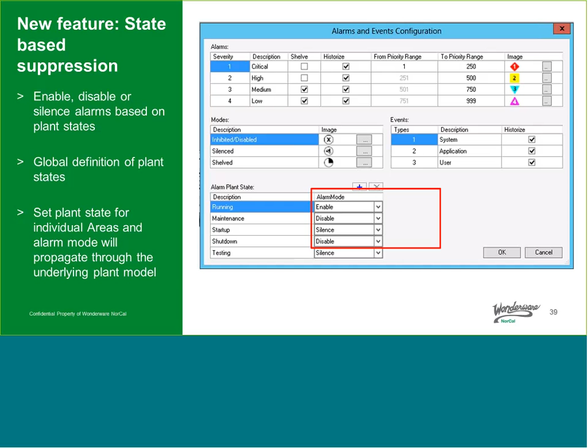If you're putting a plant in maintenance mode or testing, you can snooze or shelve an alarm. After a given period of time, the alarm automatically becomes active again, so while it's shelved or snoozed you won't see it, but you don't have to remember to turn it back on.